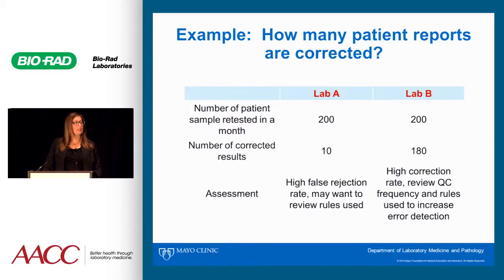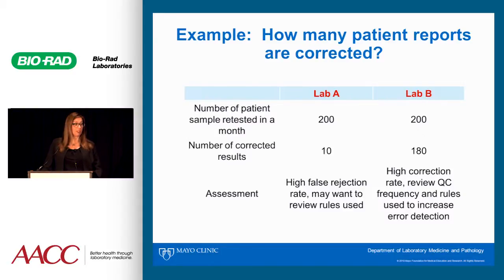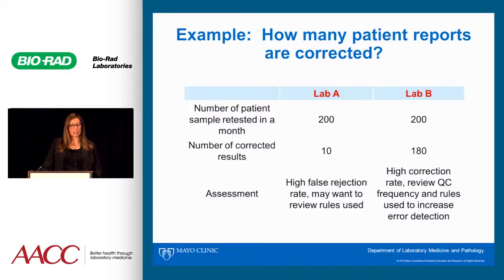However, Lab A only had to correct 10 patient results, while Lab B had to correct 180. If I'm Lab A reviewing this data, I might say I have a high false rejection rate — I'm repeating a lot of patient results when there's an out-of-control condition that don't need revision, and I might want to review the QC rules I'm using. If I direct Lab B, I'd say that's a pretty high correction rate, and I might want to review my QC frequency, my rules, and try to get rules that give me better error detection.